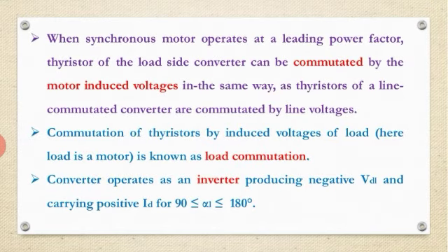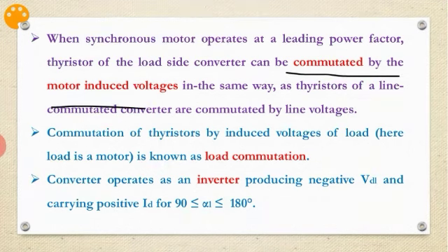Next, when the synchronous motor operates at a leading power factor, the thyristors of the load side converter can be commutated by the motor induced voltage, in the same way as the thyristors of a line commutated converter are commutated by the line voltage.